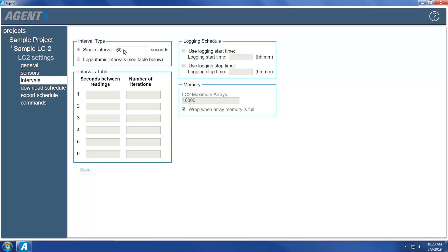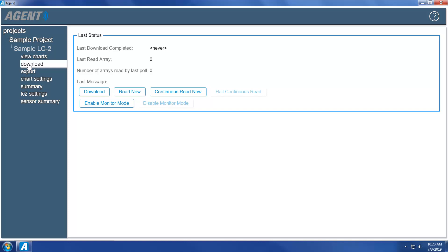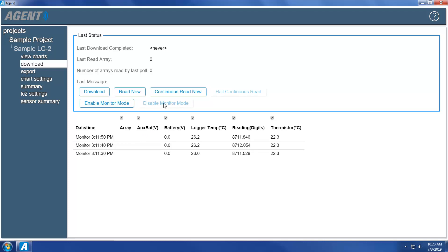The data being logged by the LC2 may be viewed as it is collected by using Monitor Mode. To enable Monitor Mode, click on the name of the LC2 to return to the main LC2 menu, and then click Download. Next, click Enable Monitor Mode. Sensor readings taken by the LC2 will be displayed on the lower half of the screen as they occur. Click Disable Monitor Mode to stop viewing the readings — note that this does not stop the logger from taking readings, it only stops Agent from displaying them. Readings displayed using Monitor Mode will not be saved to the Agent database until they are downloaded from the LC2.